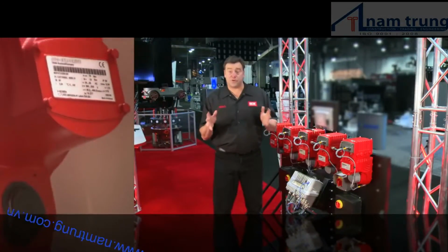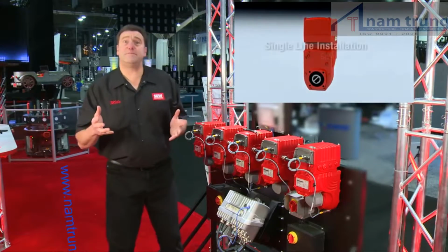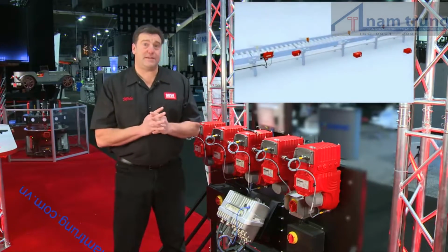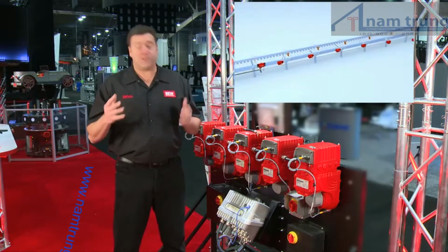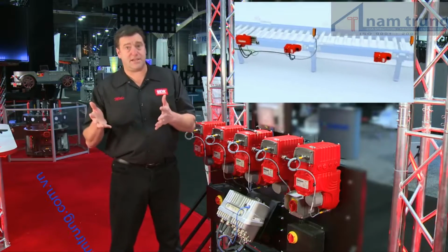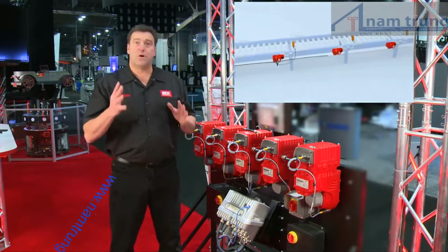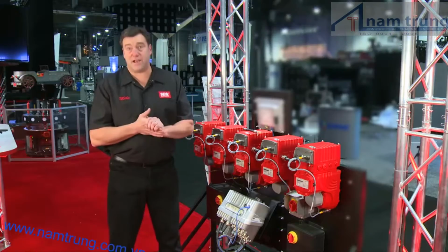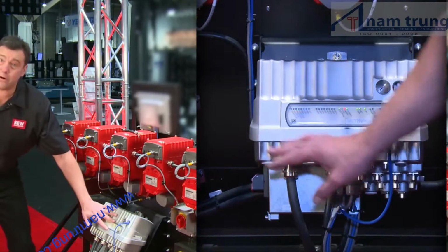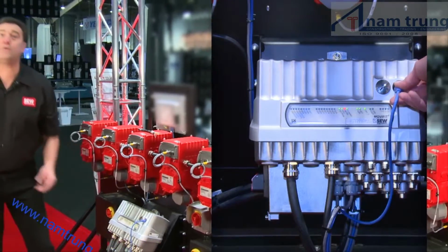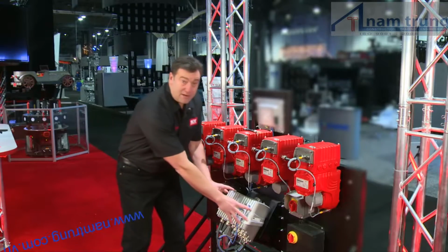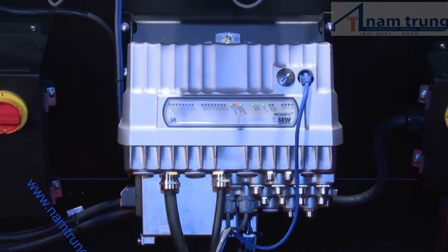There are 3 ways to control a MOVIGEAR. The first is the simplest, basically with binary control. This allows you to have 4 fixed speed set points. The next way is to use our FDC controller, which allows us to communicate with either 16 units over our S-Bus or 10 units over our special SNI network. The FDC controller consists of a disconnect, remote I/O, and a communication gateway with either Ethernet/IP or Profinet, all in a nice tight little box for decentralized mounting.